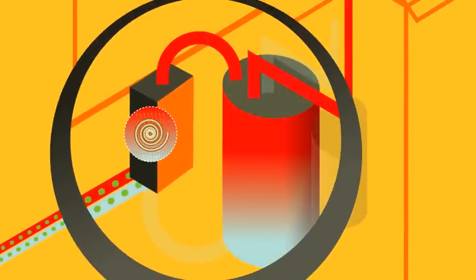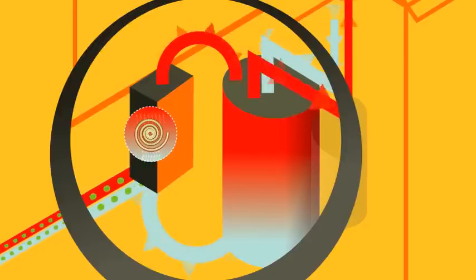As the water heats up in the heat exchanger it expands, gets lighter and rises through a flex pipe to the top of the Sunward solar storage tank. Cold water from the bottom of the tank flows into the heat exchanger to take its place.